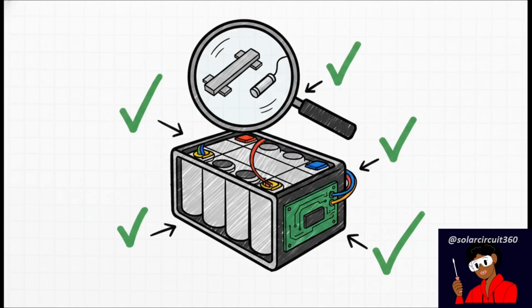First, verify the system polarity. Then, check every single bus bar connection. Confirm that BMS wiring one more time just to be sure. Inspect your cable routing and your insulation barriers. And finally, validate that your main fuse is properly installed right near that positive battery terminal. Only after every single one of these rigorous checks is ticked off should you even think about starting that first charging cycle.